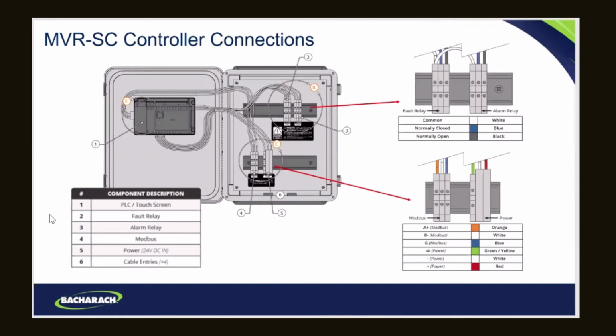So this is the inside look at the controller. And really, the brains of the controller is just this HMI that we have in here. It handles all of the networking and the logistics behind it. We put it inside this enclosure because we have to have some more stuff. We have to have input power, and the power to the controller is 24 volts DC. Here's your Modbus wiring inside the controller. So the controller is a Modbus master, but you're going to be coming out of this with an Ethernet port.